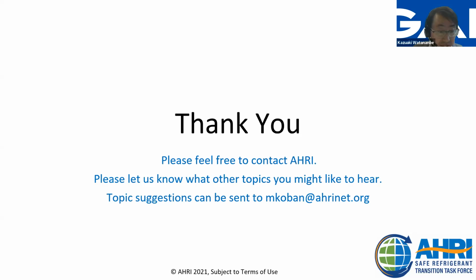Kaz, maybe you're on mute. Yeah, sorry. Yeah, definitely. So when the RDS fails, the fan or blower runs all the time, so it works with safe operation. And you can reconfirm that also holds if there is a refrigerant leak, right? Right. If there is a refrigerant leak, HVAC may continue limited operation safely until shutdown or repair.